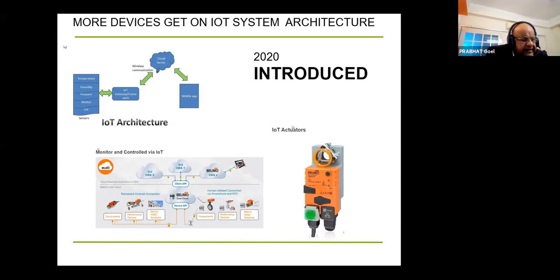Easier said than done—this was hard to track on our normal IBMS or BMS systems. Sometimes the screens weren't formatted, sometimes the analytics weren't put in. But now with this kind of system, it will be very easy to make out if the system pressure in a building is set up properly. If you set up a very high system pressure, possibly a good number of the valves will never reach a full open position, and you'd be wasting energy.